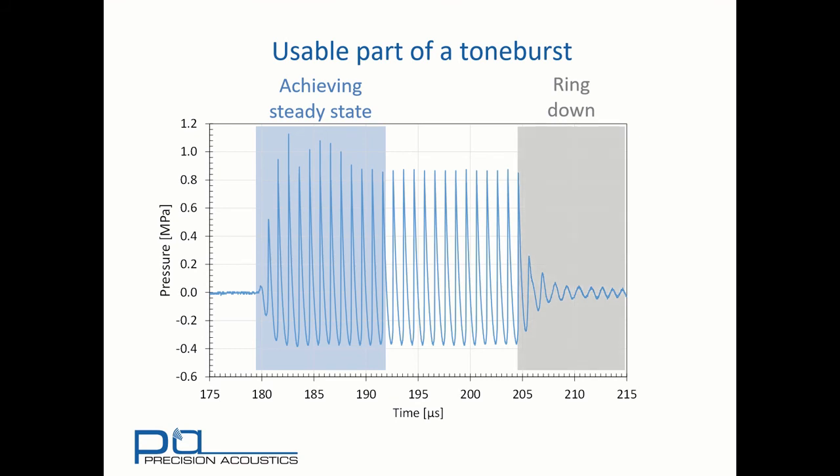Similarly, at the back of the pulse, we can see there's a lot of transducer ring down. So it's only the middle 13 to 24 cycles of this signal, which are suitable in which to make measurements.